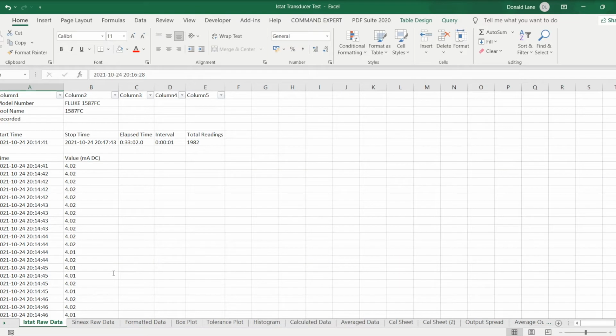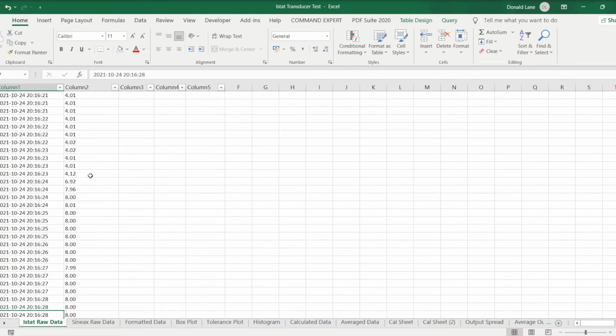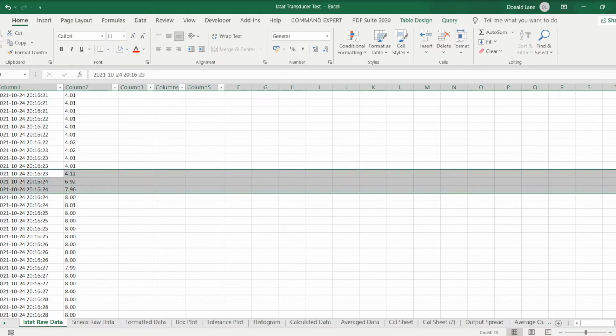Okay, so this is the data pulled into the computer, sitting here in Excel. This is how it comes in under its default format here. As it was a CSV file, it's pulled in the date and time of the reading and then the actual value that it recorded. The first element that I have to do is to remove where the meter had a step change. So if I go down to here, you can see coming down at 4 milliamps here. You can see it starts to change to 4.12, 6.92, 7.96, and then on to 8. So I will remove these 3 lines here before I do any analysis, because they would interfere with the actual tolerance readings that you end up calculating.